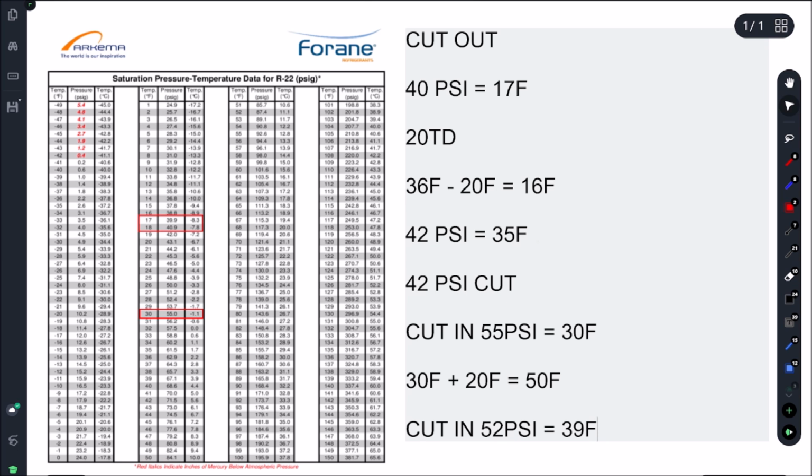Okay, I know a lot of people will get stuck on that. They'll pull up to that call and do a leak test right away. There was no need to. Okay, so we ruled out a low charge. The drain pan was not draining, so we definitely had a freeze up from there. And then also this pressure switch was an issue because we're at 35 Fahrenheit and it was still calling for cooling. So this thing probably would have pulled down to below 30.